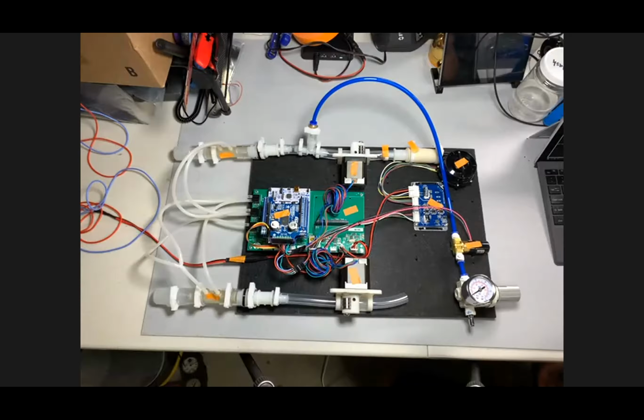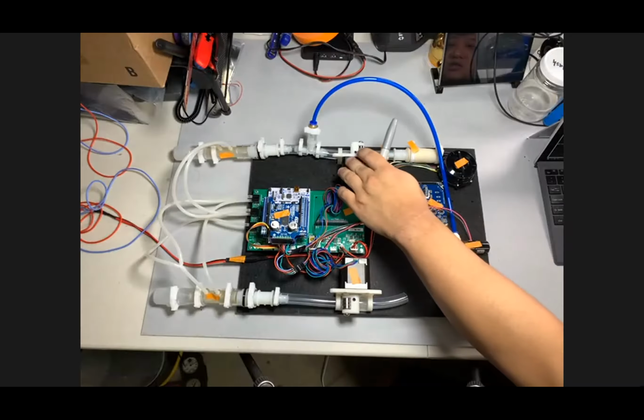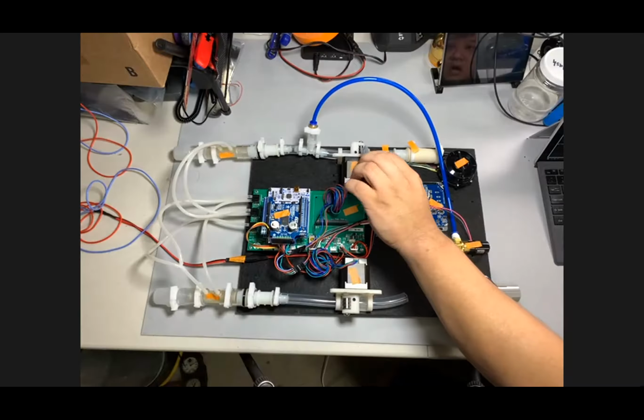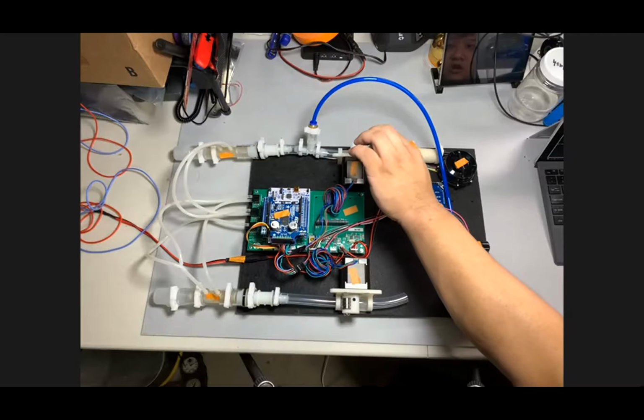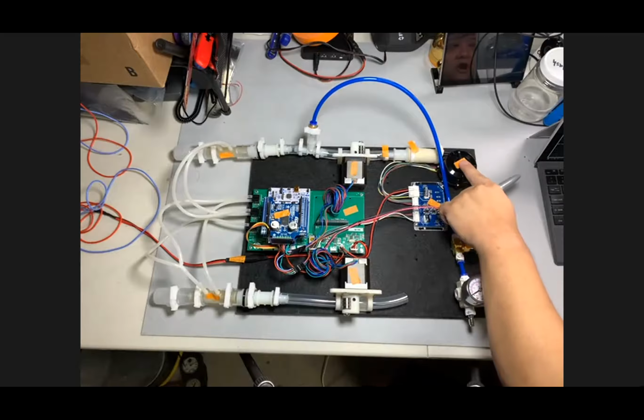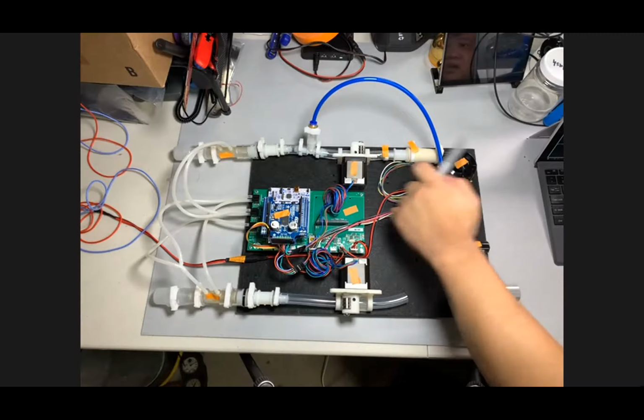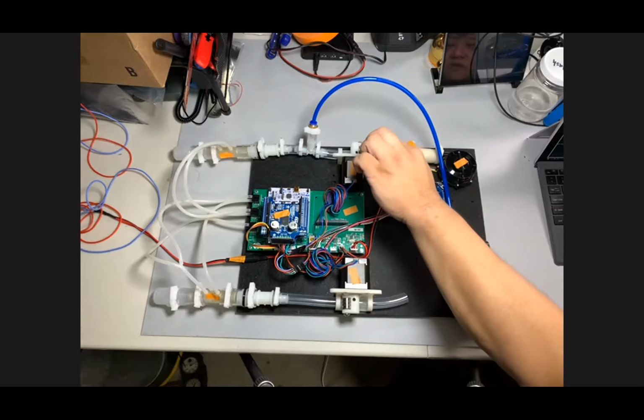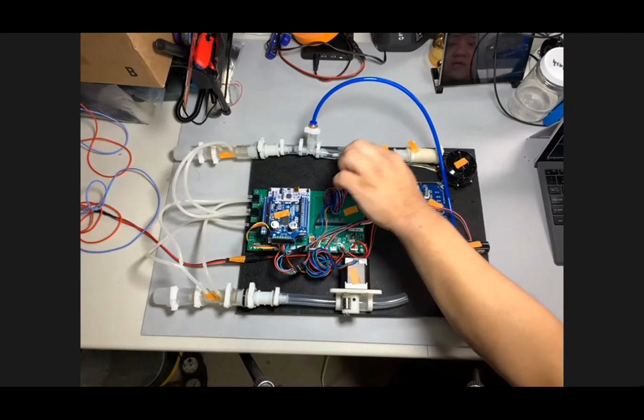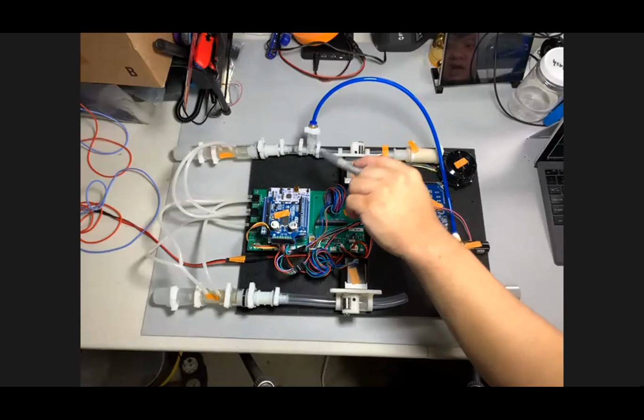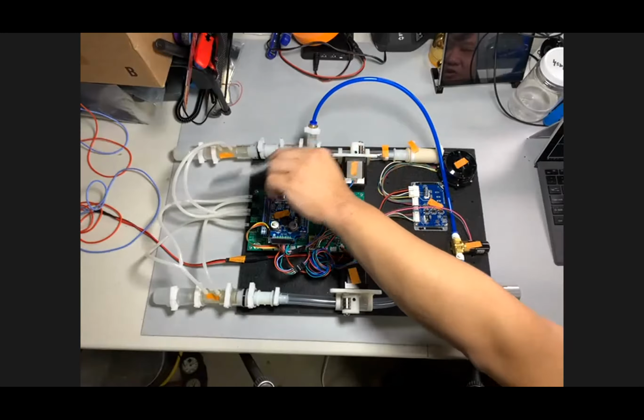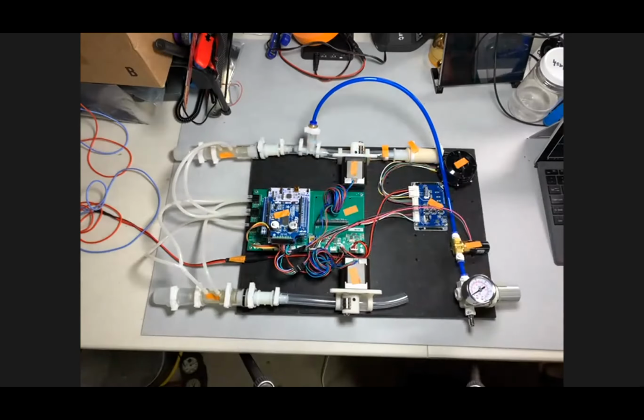What we're hoping to rely on is the differential pressure across the pinch valve. Keeping the blower on at full throttle all the time means that as long as the pinch valve is at least somewhat closed, there's going to be a differential pressure across it, and the pressure going out to the patient will be the smaller of those pressures. So we expect the flow to go only in that direction. That's something we have to verify, but for now, that's the plan.